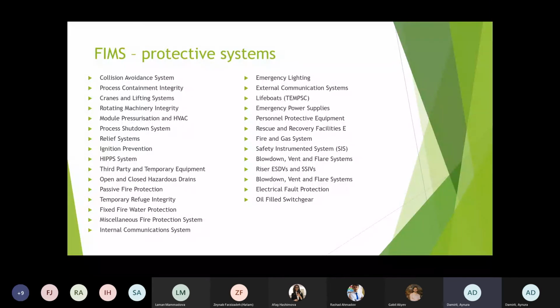And safety instrumented systems, you are already a little bit familiar with this. It's one of the main safety critical systems within facility integrity management. The goal is to detect and respond to predetermined trip criteria, and to initiate various levels of manual and automatic isolation and shutdown of process plant equipment and the wells in a safe and orderly manner.